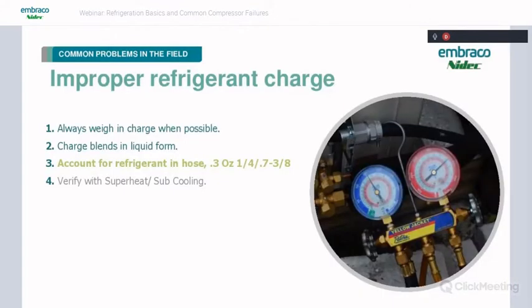And then we see improper refrigerant charges. We always want to weigh in the charge whenever possible. It's basically mandatory with these very small systems that have real tiny charges. If we're using a blend, we need to charge that in liquid form so we don't fractionate the blend, because you can actually get more of one molecule than the other, and then you don't know what you have in there. The system's not working correctly because the blend is not at the right ratio.